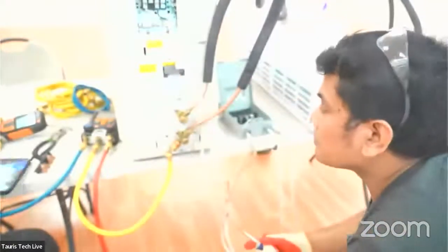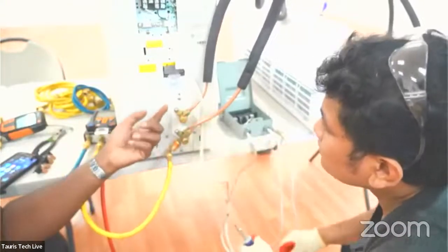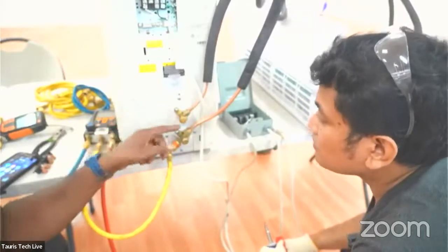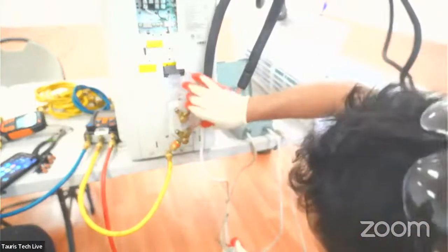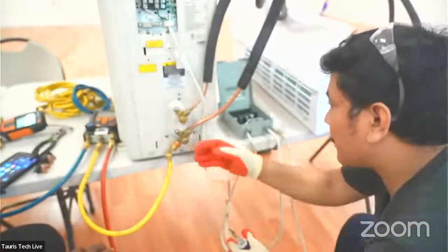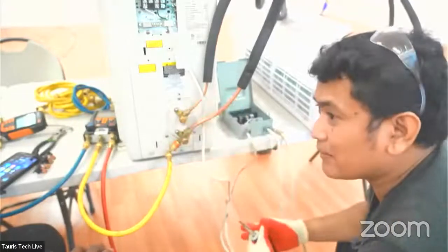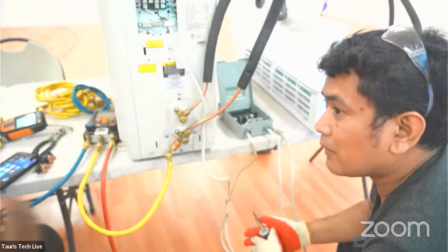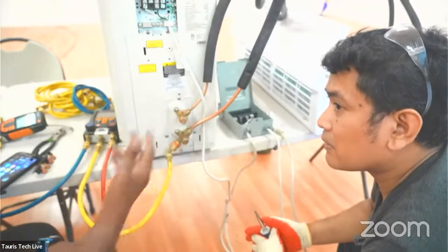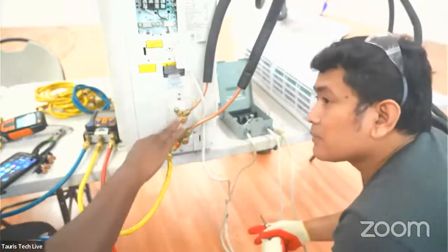That's oil, because we take it on and off a lot. Usually if you're looking for a leak and you see oil, that's an indication of where your leak is coming from. But this one is disconnected, right? Yes. So none of this is going to be connected. What's the easy way to find this? This is the liquid line. We reuse the machines when we teach, and when they don't connect it right, the oil comes out. Okay. But usually you shouldn't see anything.